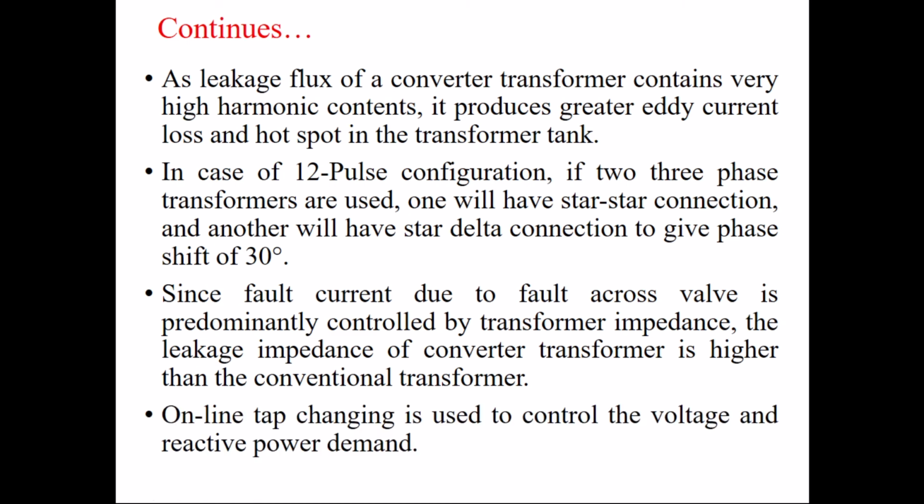As well as here in this converter transformer, we provide an online tap changing facility to control the voltage, because we know that in the converter we change the voltage. By changing the voltage we control the voltage. So periodically the converter changes the voltage, and from the supply side we require different voltage levels. That's why we need to provide the online tap changing facility. That not only controls the voltage, it also provides reactive support to the system.